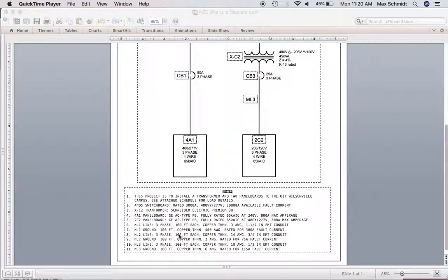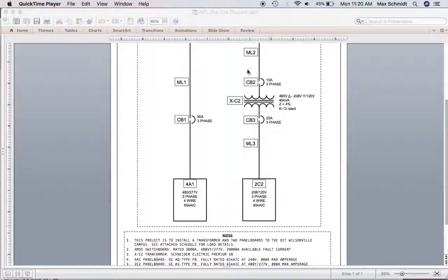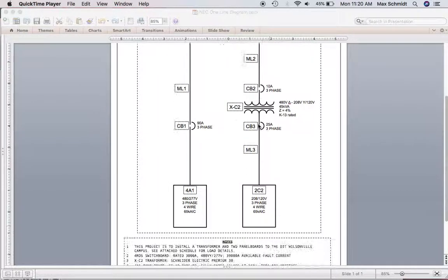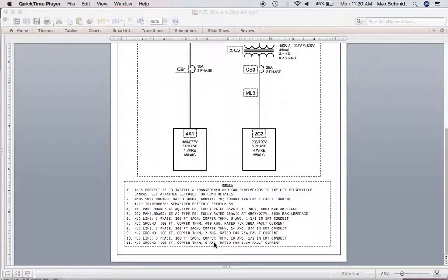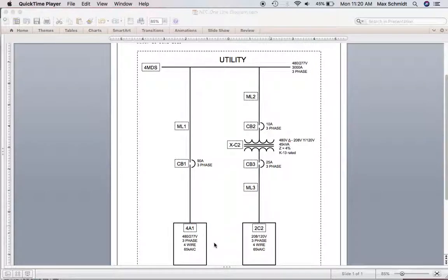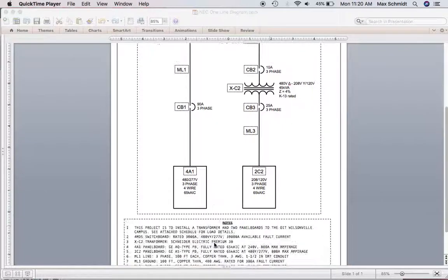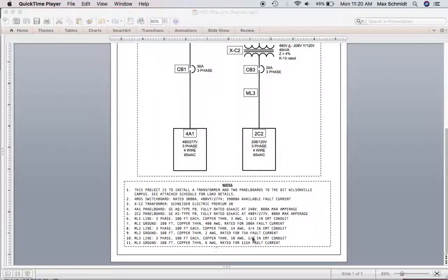Those are pretty straightforward, and then there's a little more detail for the lines, so I have that provided down here. So main line 2 details are as follows, and these are going to be a little smaller. There's less current going through here, and then as the voltage is stepped down across this transformer, the current goes up. So then I've rated those for higher values as well. This may change. I haven't done my sizing for my load wiring or my conduits there. So if it's cheaper to buy those in bulk, I may change these gauges. But these are the minimum required ones for all 3 of these main lines.